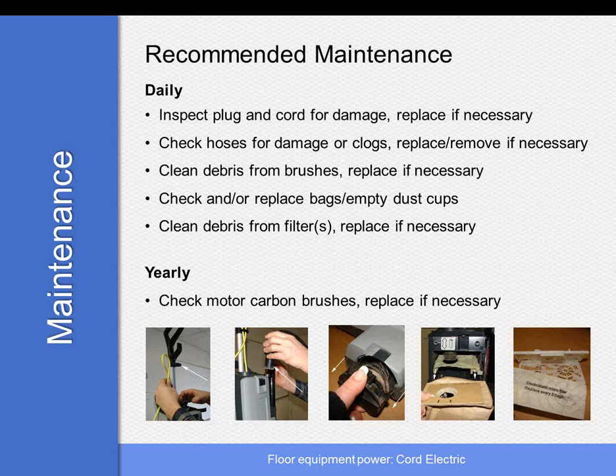Yearly, we want to check the carbon brushes and replace them if necessary. Normally on a vac motor or a brush motor, you replace the carbon brushes once, you're good to go. If you keep it up to where you have to replace them a second time, it might be about time to replace the motor.